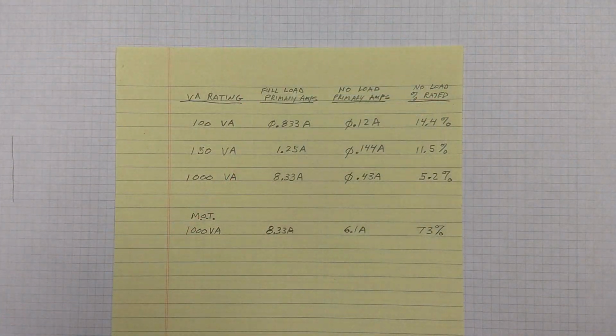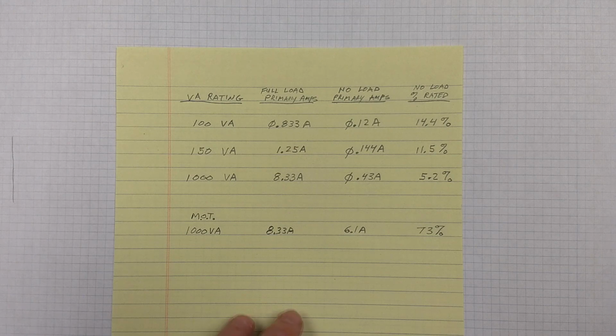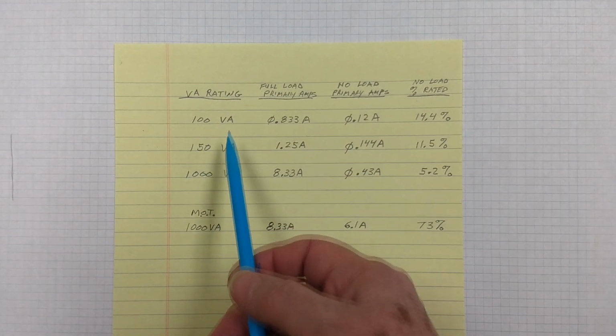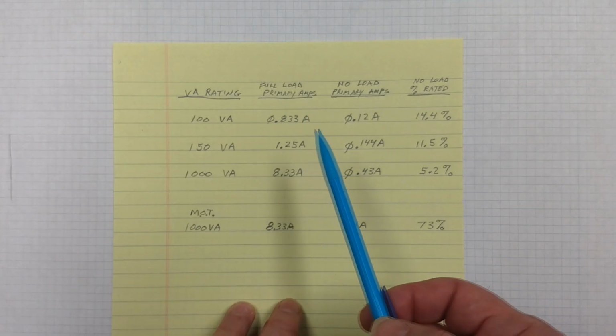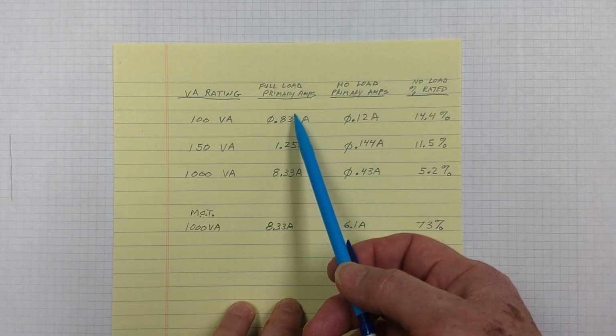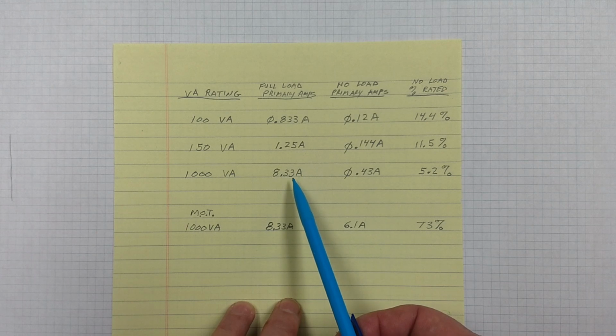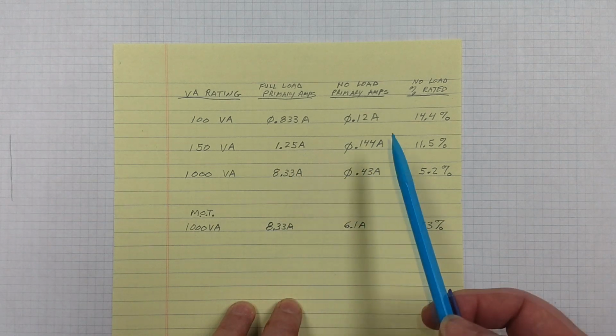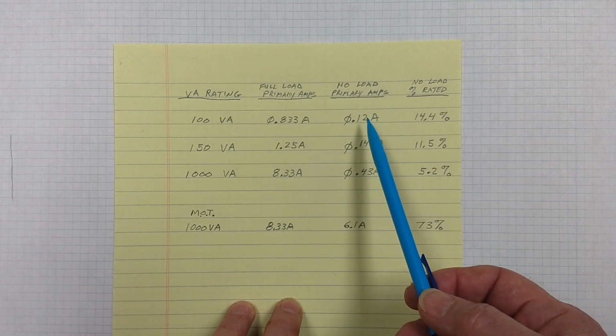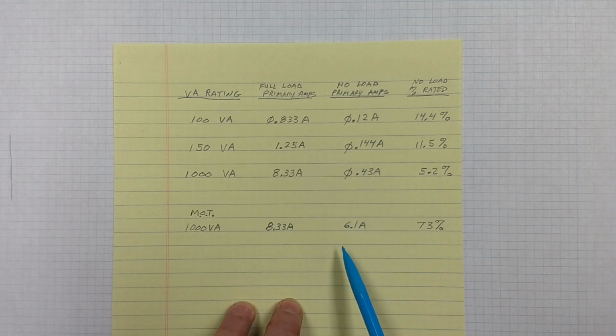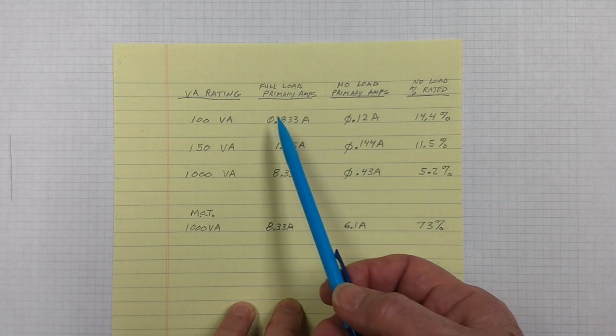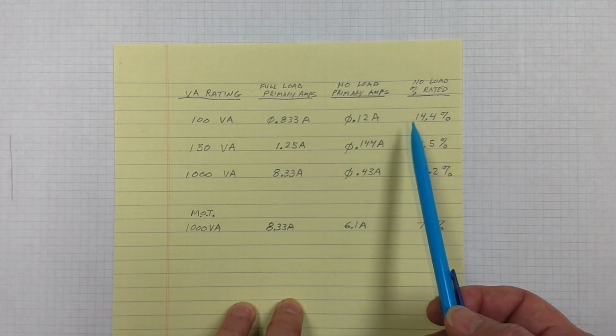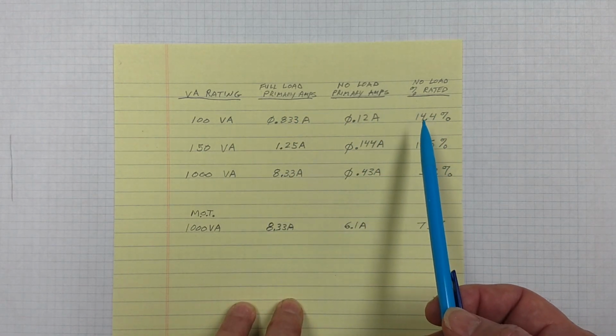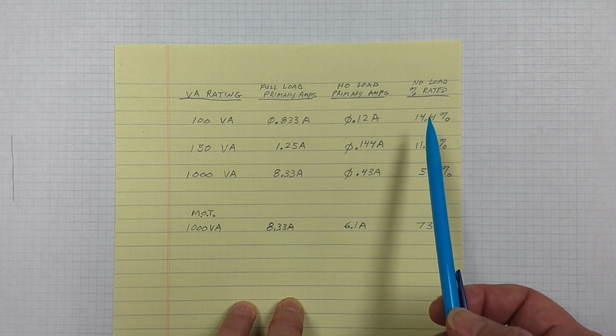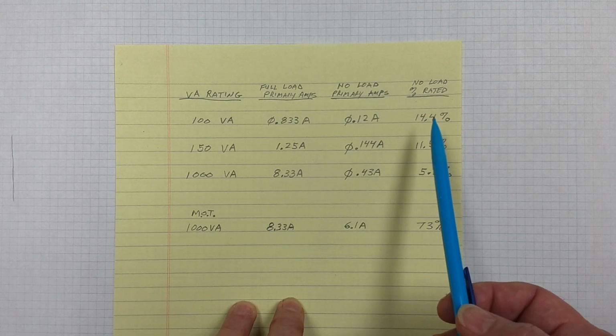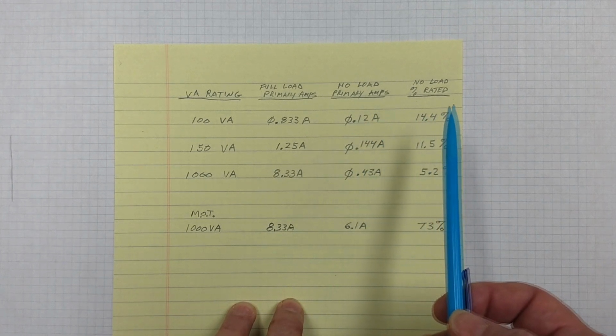Okay, I ran some tests on some other transformers as well of various volt amp ratings, and here would be the normal full load primary current, and here are the currents under the no load conditions. Here's the transformer that we just looked at, and we can see we get a current of 14% of its full load rating with no load connected.